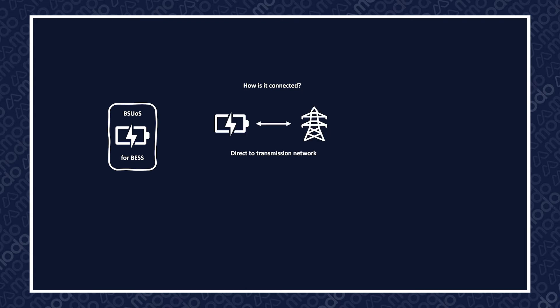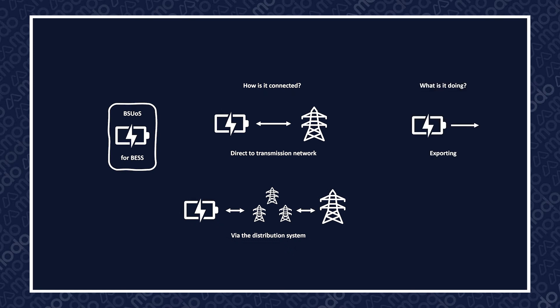Connection can be either directly or via a distribution network. The second factor concerns whether an asset is exporting or importing energy. No BSUOS is charged on import for BESS. This has not always been the case, and batteries did used to be subject to double charging, meaning they paid BSUOS on both import and export.